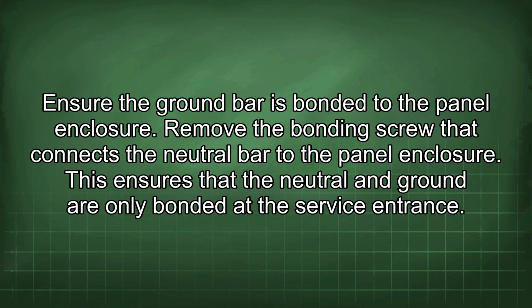Remove the bonding screw that connects the neutral bar to the panel enclosure. This ensures that the neutral and ground are only bonded at the service entrance.